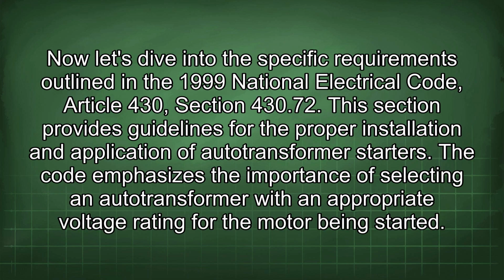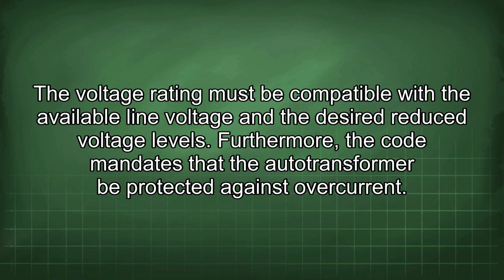Now let's dive into the specific requirements outlined in the 1999 National Electrical Code, Article 430, Section 430.72. This section provides guidelines for the proper installation and application of autotransformer starters. The code emphasizes the importance of selecting an autotransformer with an appropriate voltage rating for the motor being started. The voltage rating must be compatible with the available line voltage and the desired reduced voltage levels.